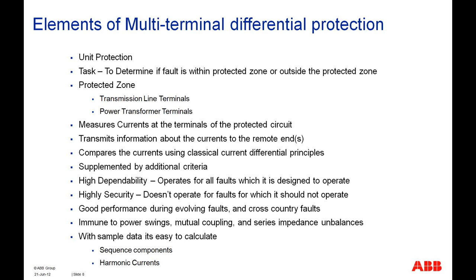In line differential protection, you can obviously have an element of equipment, a transmission line, which needs to be protected, but also in certain cases you have the power transformer within the protection zone as well. Having a power transformer within the protection zone of line differential protection imposes some more issues, and those issues need to be addressed, and we will talk about it.